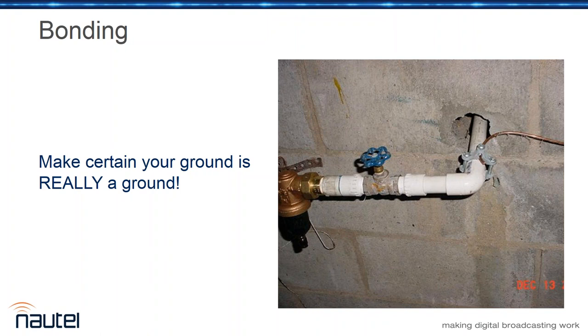So by all means, make sure you actually are connected to ground. In the lesser extreme, a lot of times I'll walk into a site and see everything connected to a nice reference ground point in the room. Then you'll discover that the ground was from an old install and it doesn't actually go anywhere, it drops into a cable trough and just ends. So make sure ground is actually connected to earth somewhere.